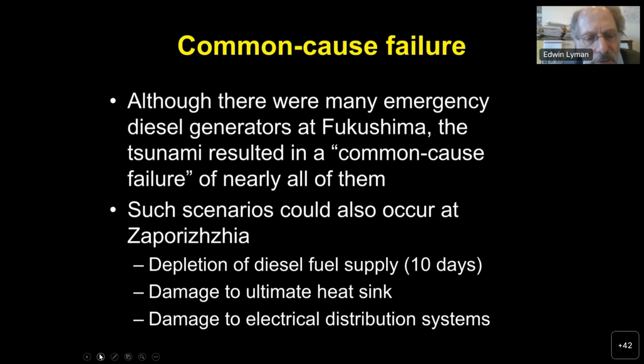You could also take out the ultimate heat sink, and those diesel generators, in order to function, generate heat of their own. And you have to keep the temperature in the diesel generator hall below a certain temperature so you don't destroy the diesel generators. That means that heat has to be taken away from the site and deposited in the environment. And so if that ultimate heat sink is disabled, you could take out all the diesel generators at once.